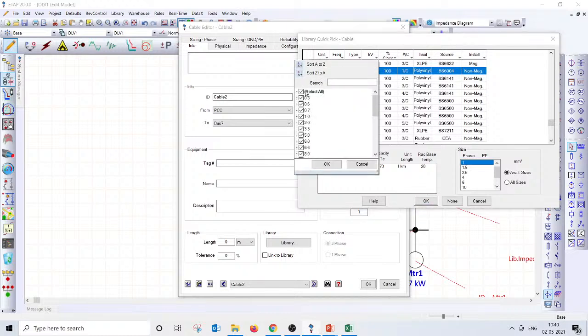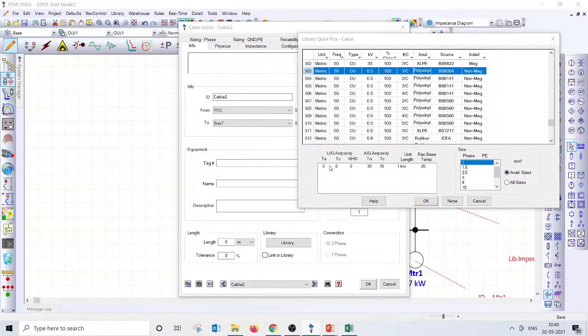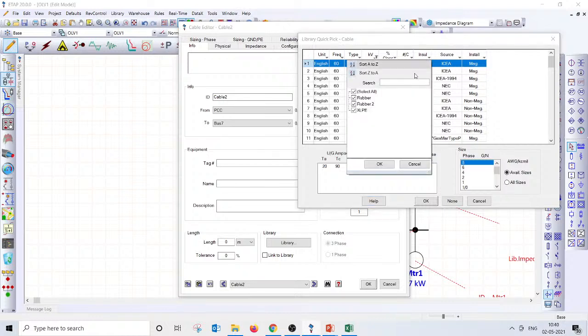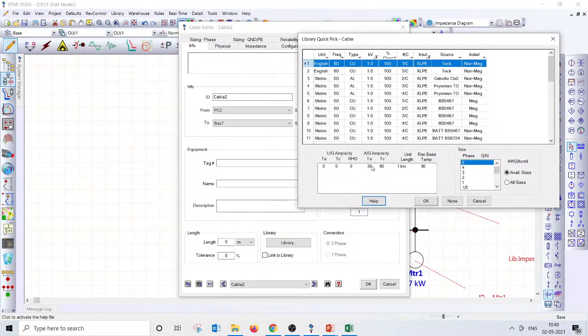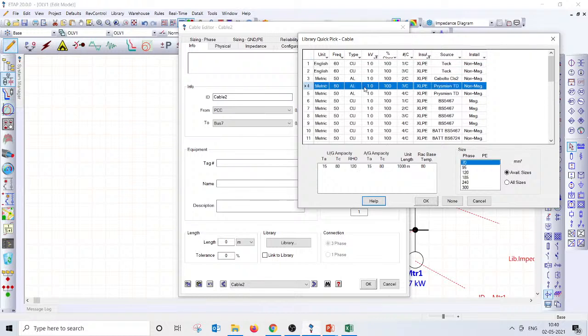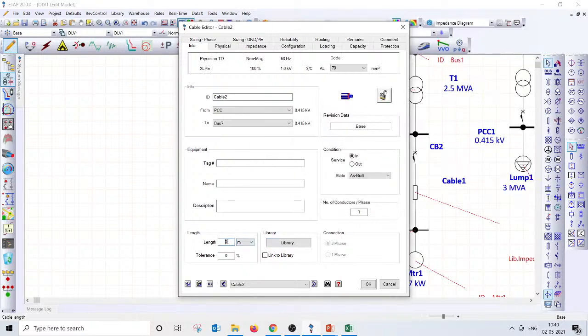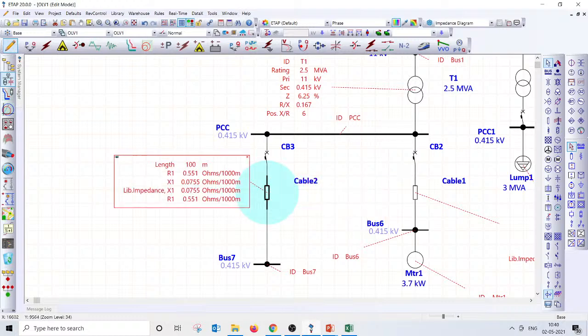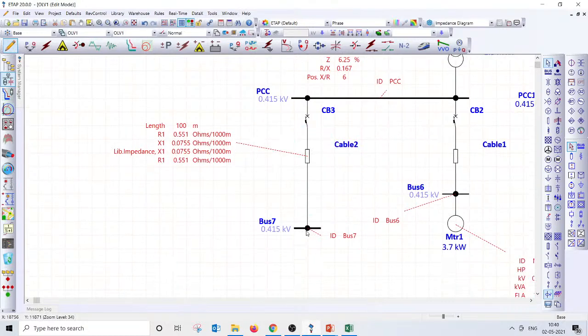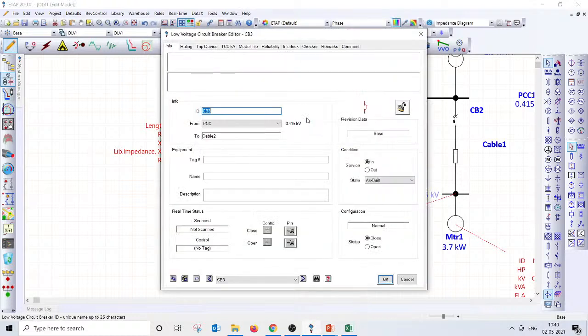Let's always take a 1 kV grade cable, always with XLPE insulation, aluminum, right? 70 square mm. That's great. Assuming again 100 meters. Good. So here, if you look at this, we need to give the fault current and the delay time. Here you might be connecting quite a lot of motors, and you need to coordinate them well.